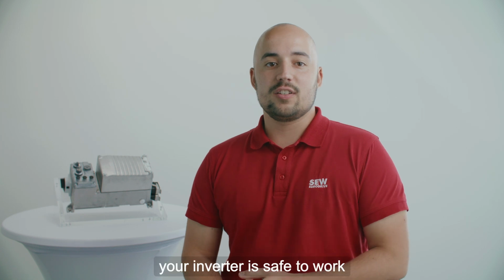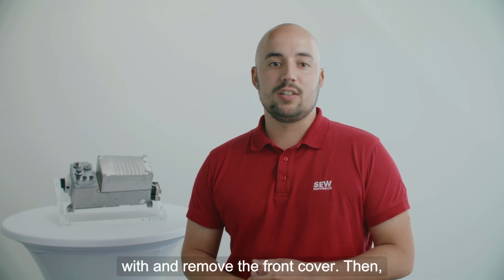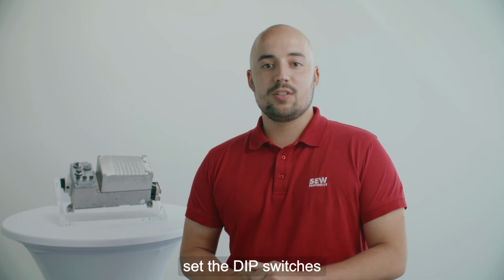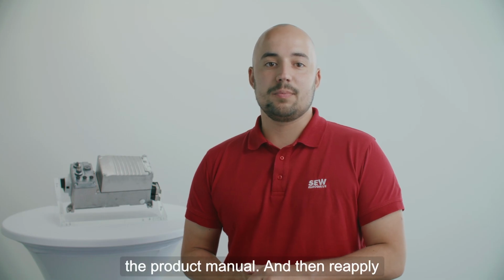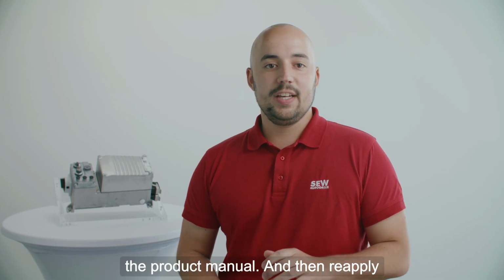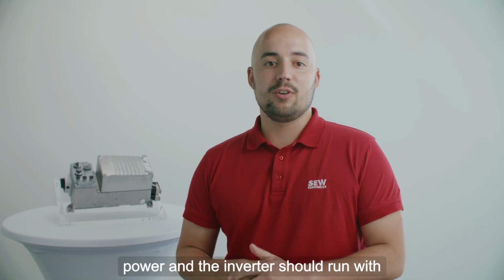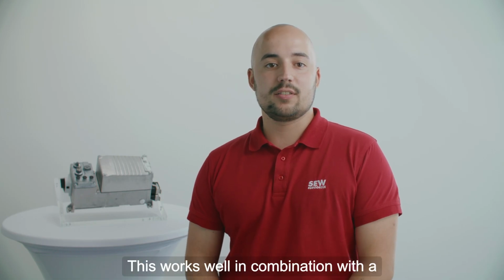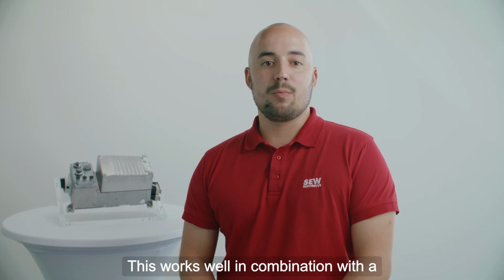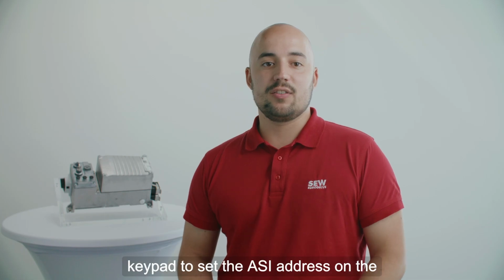First, make sure your inverter is safe to work with and remove the front cover. Then set the dip switches according to the startup table in the product manual. And then reapply power, and the inverter should run with the predefined parameters. This works well in combination with a keypad to set the ASI address on the inverter.